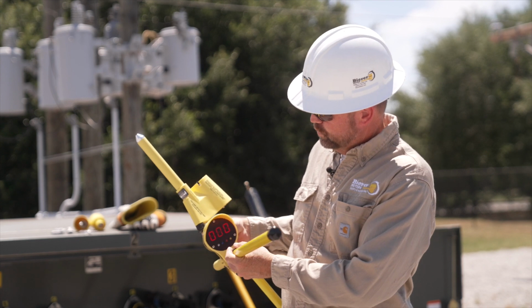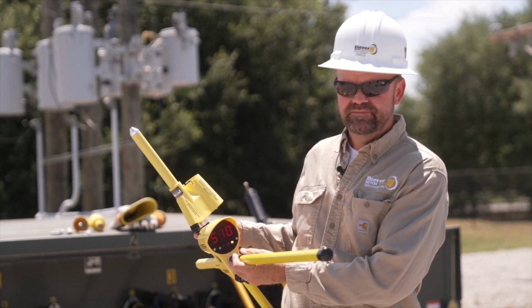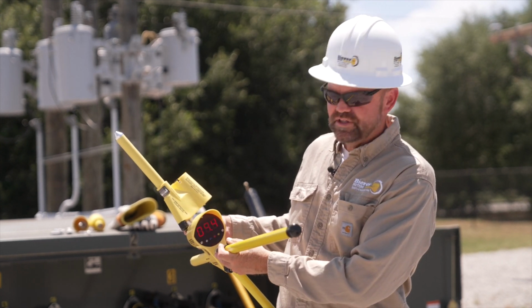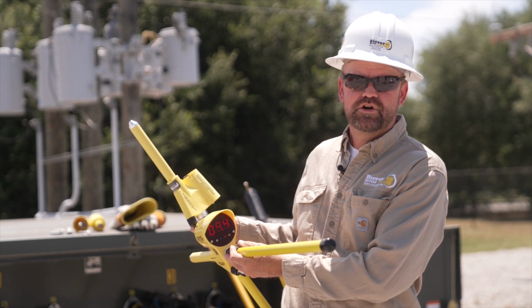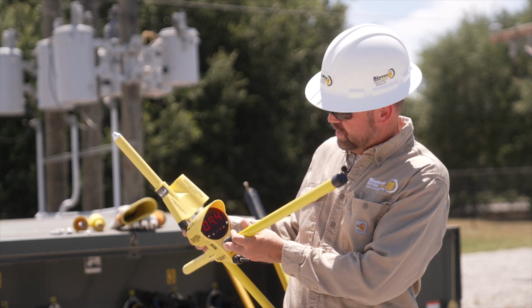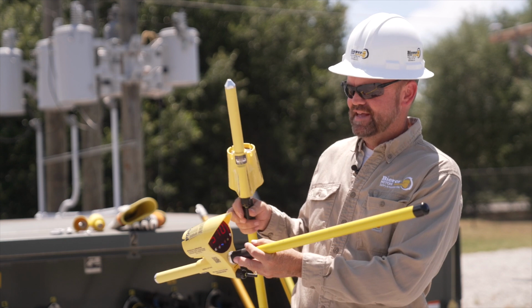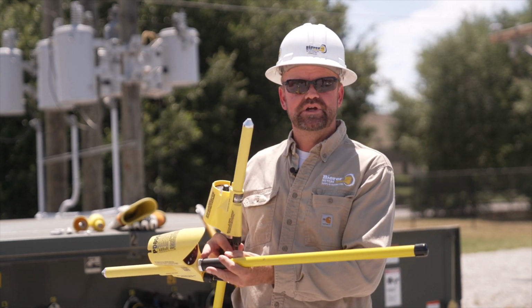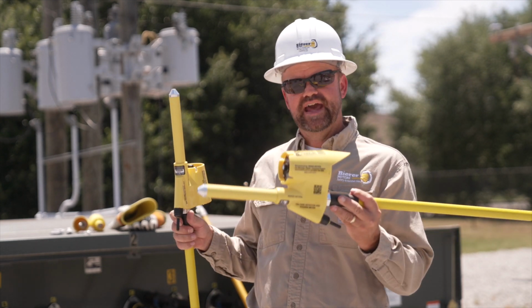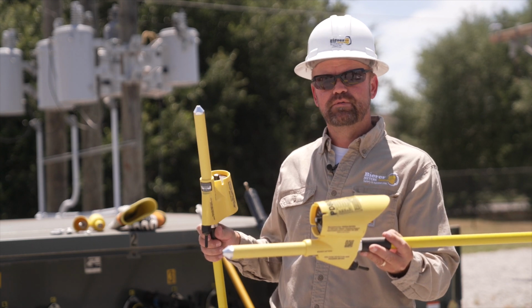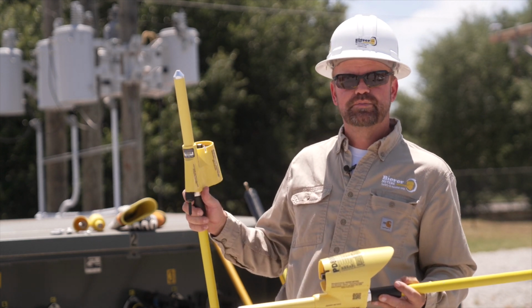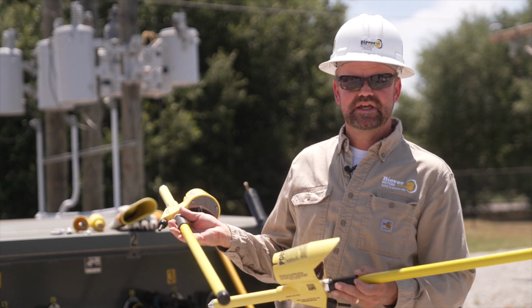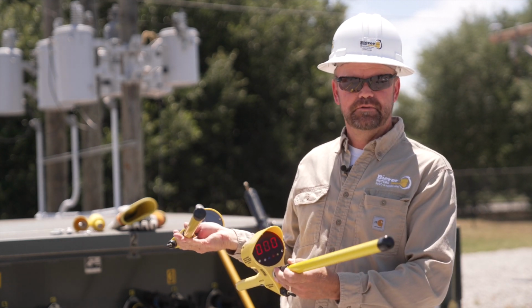If I hold the tool over to the test position, it reads the battery voltage. So that's the internal battery voltage of the tool. It's over 9 volts. It has a 9-volt battery here behind the quick change. So that's testing this meter probe, but to test the reference probe, I essentially do the exact same thing and watch the display on the meter probe.